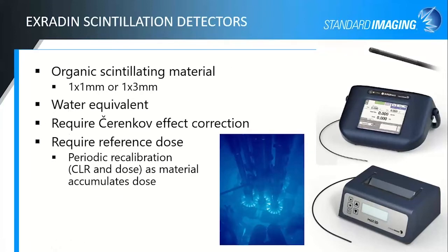The second option I'm presenting to you is our scintillation detectors. We have the W1, which has been on the market for quite some time. That is a 1 millimeter diameter, 3 millimeter long organic scintillating fiber. The more recent version of it, called the W2, has a dedicated electrometer called the Max-SD. That's the one that's shown down here. There are multiple fiber options with that one. You can get a 1 by 1 millimeter or 1 by 3 millimeter. Actually, I should say it comes with both. You can use either one, whatever is most appropriate for what you're measuring.